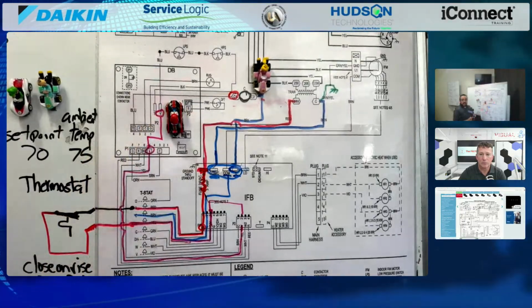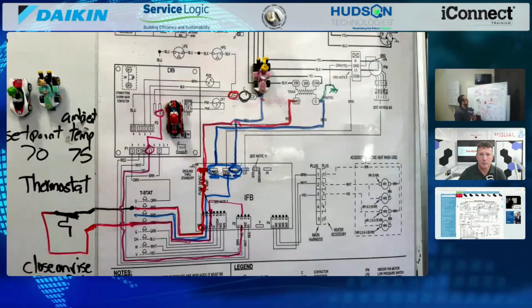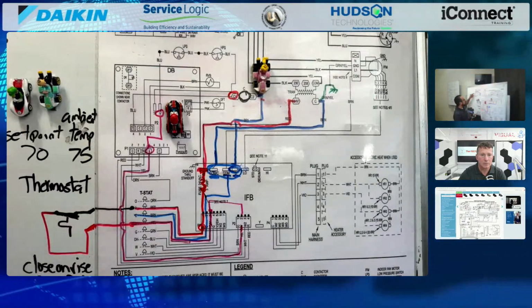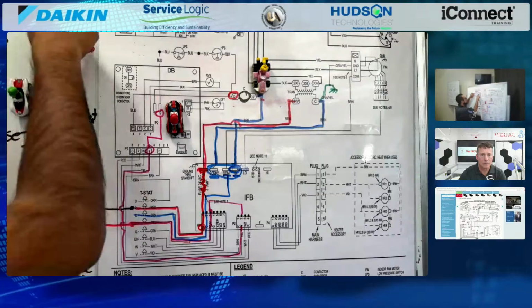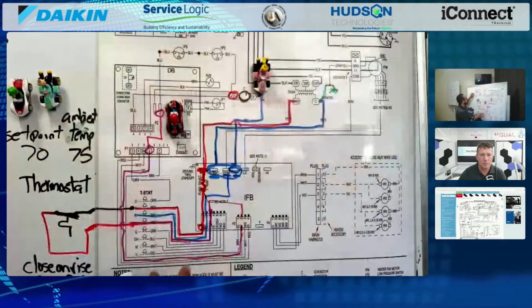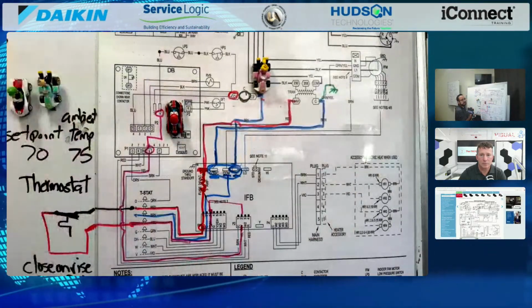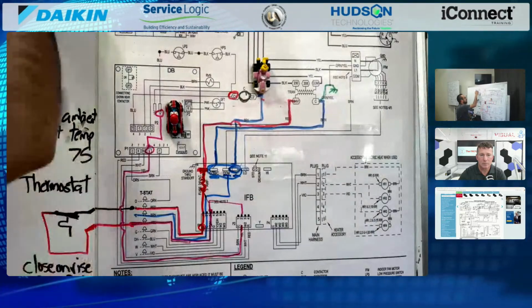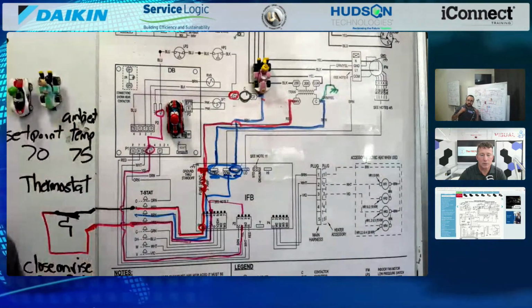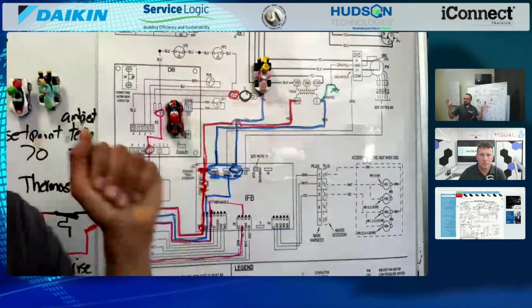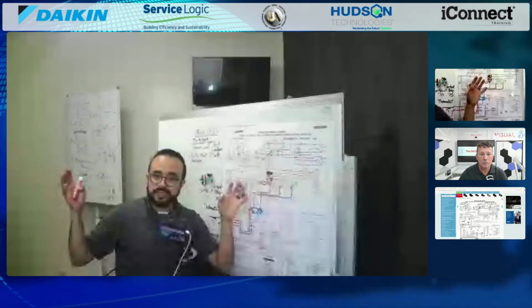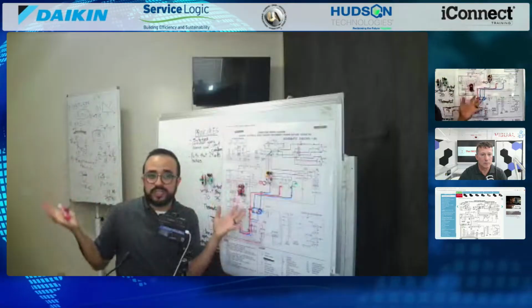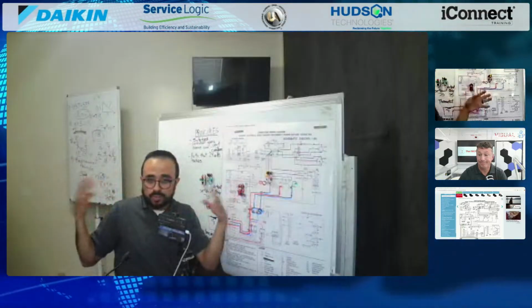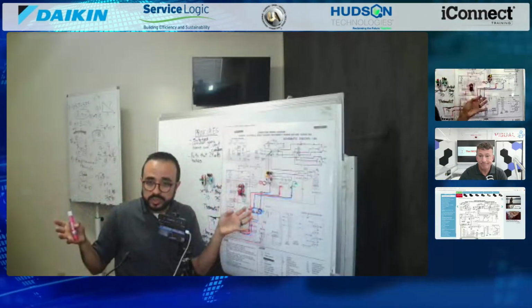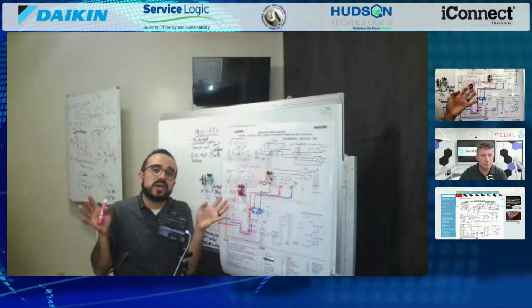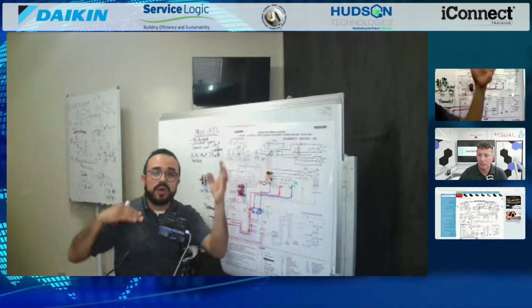Now the principle I was talking about, right? We did say that common goes to home run, and then we did say that unit is common. We're focused on the path that 24 volts takes, but the safeties are important. So even with commercial systems, if you're dealing with big systems, all it is just more safeties, whether it's a freezestat, low pressure, high pressure switch, temperature switches. It's just safeties. But guess what? It's still power in, power out.